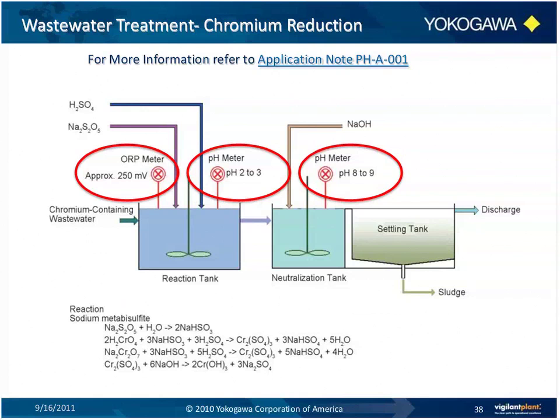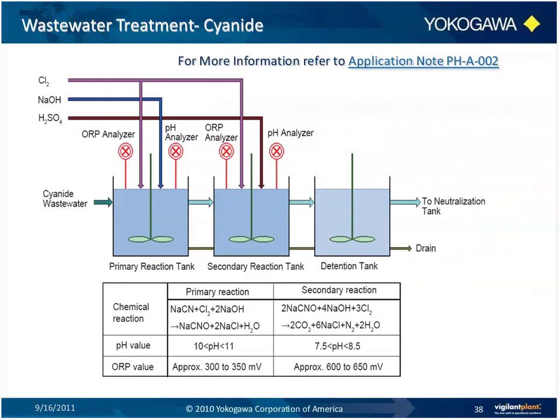Okay, and this last application that we'll discuss today is cyanide wastewater treatment. Wastewater can contain alkaline rare earth metals and other heavy metals such as iron, nickel, and zinc. Cadmium, copper, silver, and gold are also commonly seen, and sometimes it can contain a deadly poison, cyanide. Obviously, cyanide-bearing wastewater found in mining and electroplating facilities and certain types of chemical plants is toxic and must be treated by oxidation with chlorine or chloride to bring the cyanide concentration within EPA regulatory limits before it can be released into the natural wastewater stream.